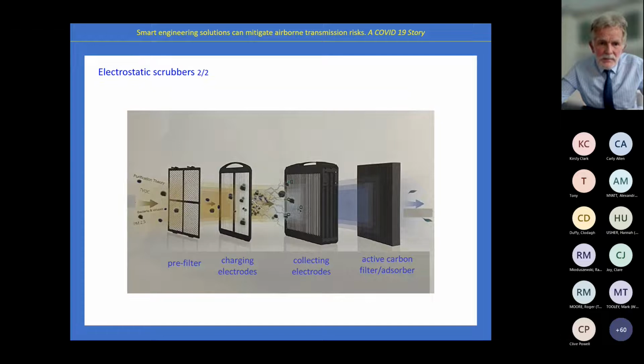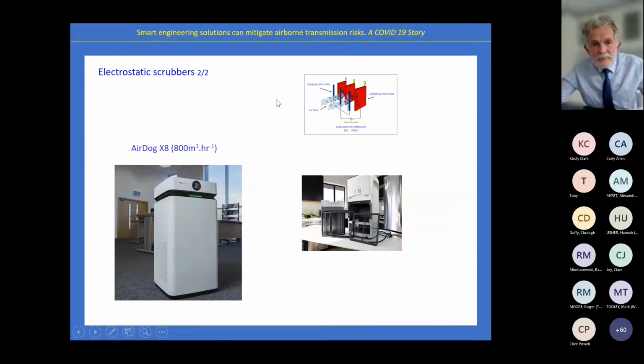This is how their machine works. Air comes in through a pre-filter just to pick up fluff, basically. It goes through a matrix of charging electrodes, putting minus 12 kV on particles. They are then spontaneously precipitated out by collecting electrodes at earth potential. The gas which exits here is free of particles, however, is likely to be contaminated with ozone. So an active carbon filter here absorbs the ozone, with the benefit also of picking up smells and volatiles and whatever that tend to be in healthcare spaces anyway. And this is the piece of kit. Shocking name, but it's quite interesting, and we're looking at this device in Liverpool at the moment.